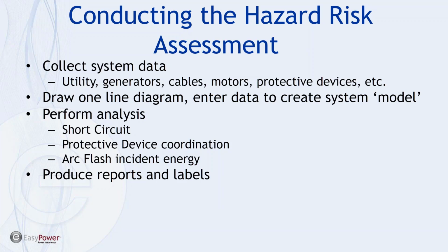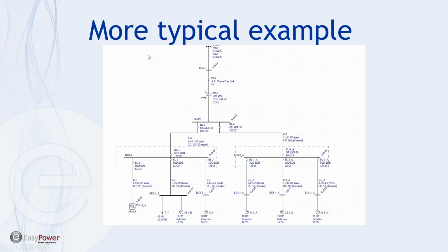So all those are key factors when we're doing the coordination. Now, as far as conducting the actual risk assessment, which is, as I mentioned earlier, just a portion of the overall compliance, we've collected the data, we've drawn a one-line diagram, and in the process, we're utilizing EasyPower tools to enter the data. This creates the digital model that allows us to do the analysis. So that's what I'm going to jump into now.